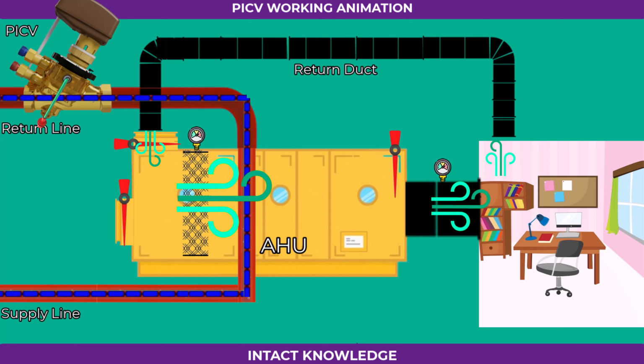Later, when the room temperature rises above the set point again, the temperature sensor once more signals the actuator to reopen the valve. Chilled water then begins to flow through the coil again, resuming the cooling process. The same principle applies not just to AHUs, but also to FCUs, fan coil units, and BCUs, blower coil units. This is the complete working concept of a pressure independent control valve, or PICV.